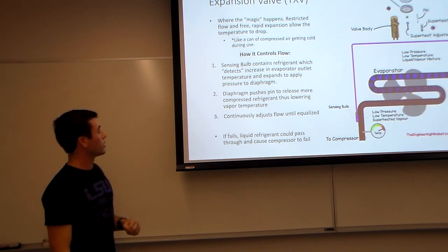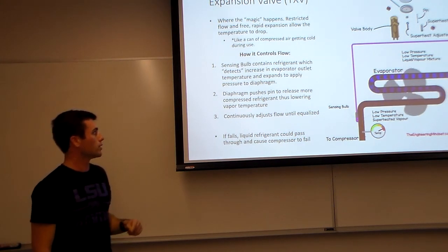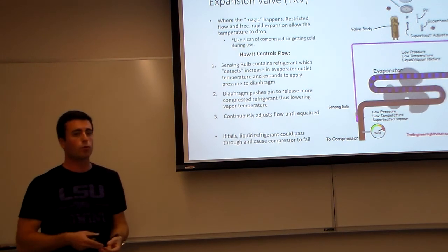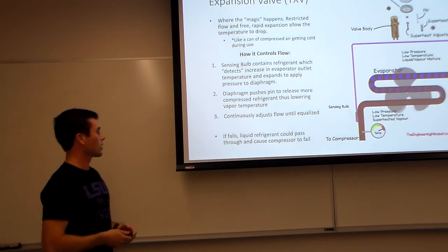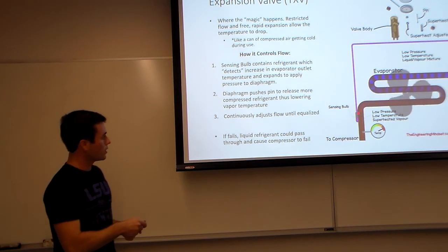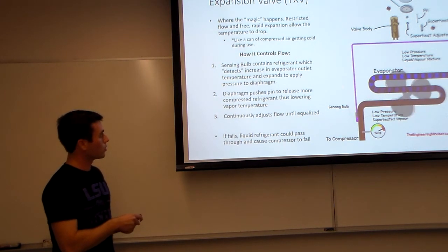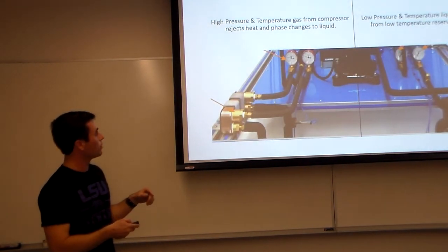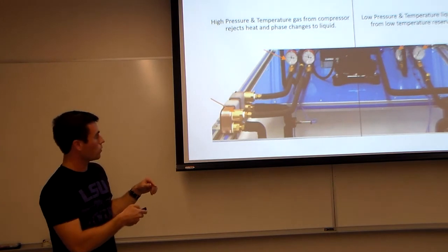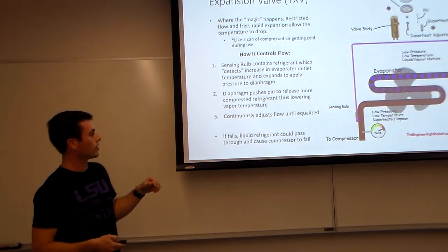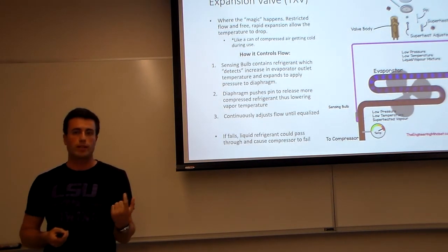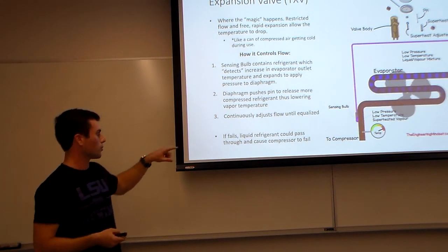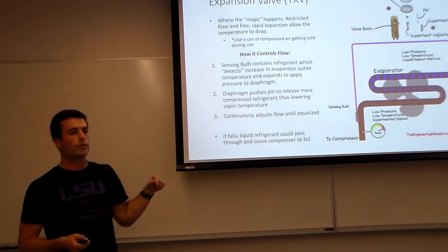So what's special about this TXV valve is it actually has an automatic control for your flow. And kind of what we're looking at here, what we're interested in, is this little sensing bulb going all the way back to your actual expansion valve, and what's cool about this is they actually have a little amount of refrigerant in that sensing bulb, and it's in thermal contact with the outlet of the evaporator.